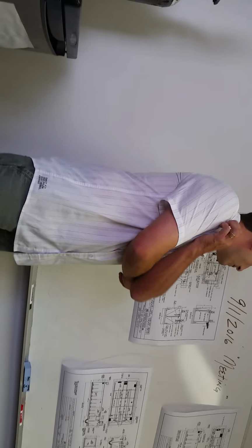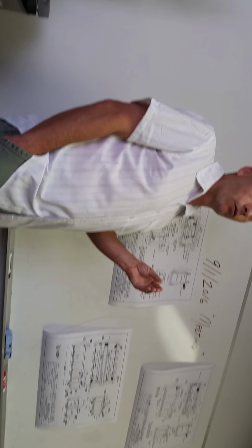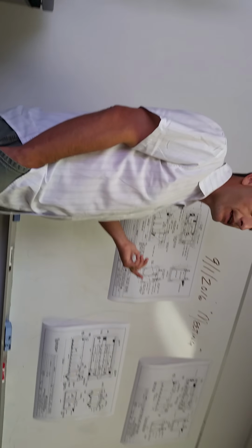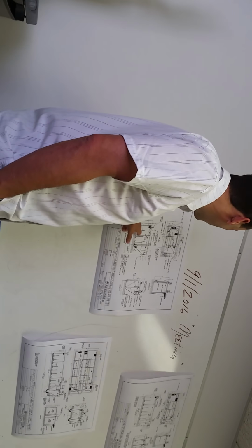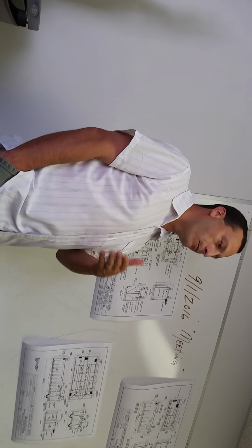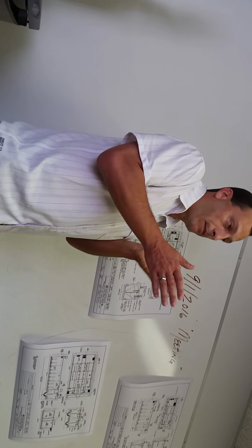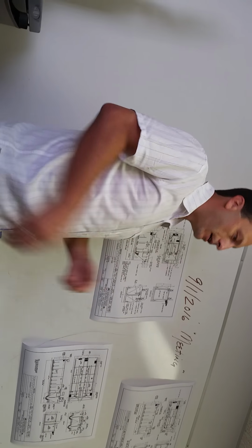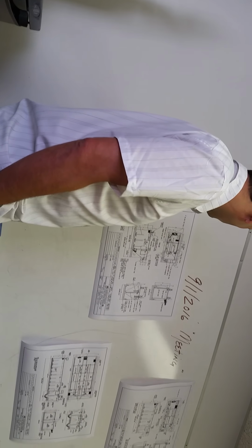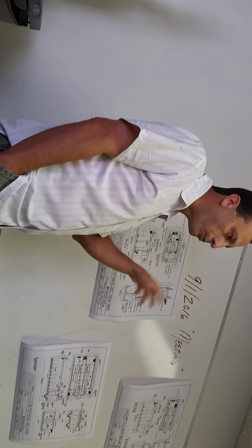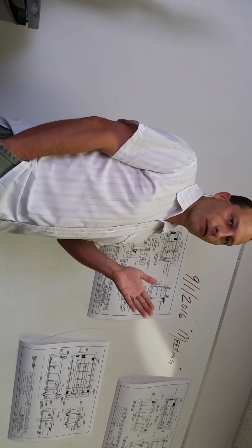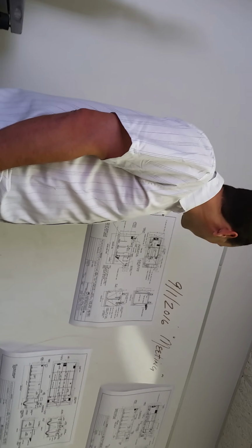I think we talked about it a little bit last week. We run the best system in a little wider mixed liquor. Typically, an EA plant's going to run in a narrower mixed liquor range. It still might be 2,000 or 2,500 as far as the concentration of solids in that tank, but instead of being run from 2,000 to 3,000, it might only swing about 150 milligrams per liter. So what they'll typically do is they've got a sludge holding tank on here. They'll just crack the valve so that every time the blower turns on, they waste a little bit, and they'll try to find that range where they maintain a consistent mixed liquor in that tank.